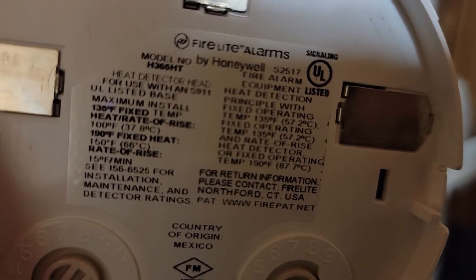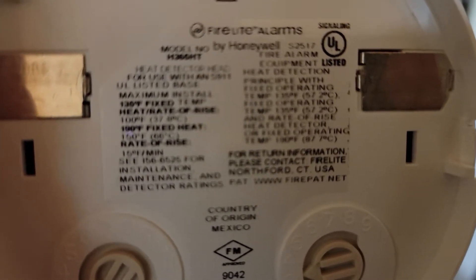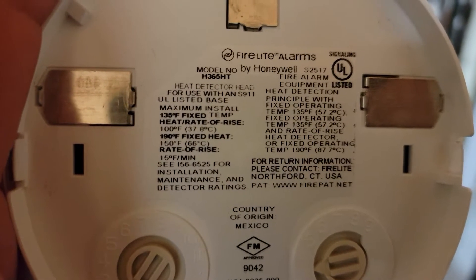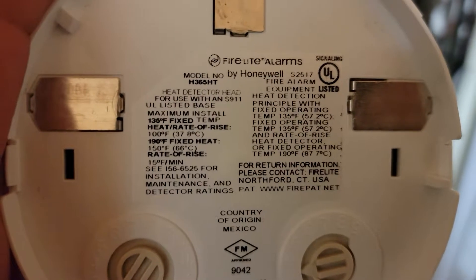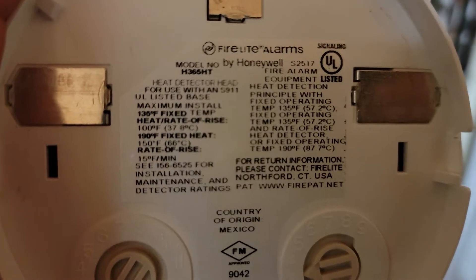So there's the detector - you can see right there, H365HT, should be 190-degree fixed temperature. But it says 150 degree F, 66°C rate of rise - that's interesting, maybe that's the problem. It says right on there 150 degree F, 66°C rate of rise. Does this actually have a rate of rise function? It's my understanding that these do not - I'm not entirely clear right now.